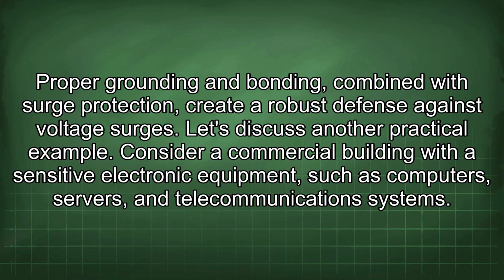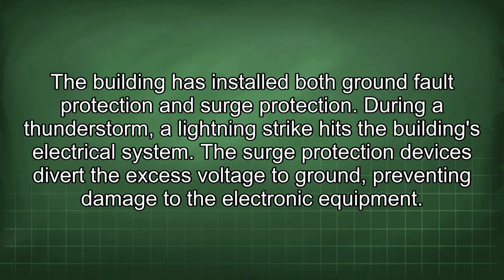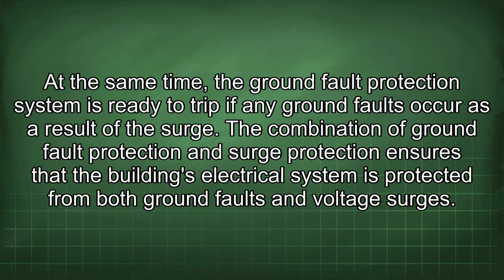Let's discuss another practical example. Consider a commercial building with sensitive electronic equipment such as computers, servers, and telecommunications systems. The building has installed both ground fault protection and surge protection. During a thunderstorm, a lightning strike hits the building's electrical system. The surge protection devices divert the excess voltage to ground, preventing damage to the electronic equipment. At the same time, the ground fault protection system is ready to trip if any ground faults occur as a result of the surge. The combination of ground fault protection and surge protection ensures that the building's electrical system is protected from both ground faults and voltage surges.